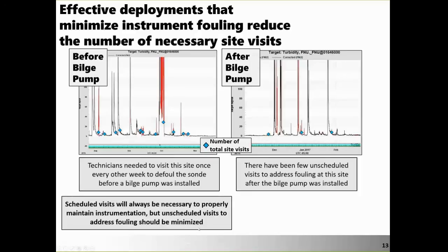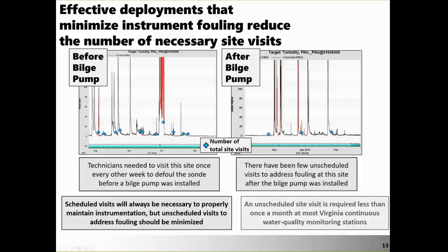There will always be scheduled visits necessary to properly maintain instrumentation, but we're trying to minimize unscheduled visits — those times we come in and see the records don't look accurate and someone has to drive out to clean the instrument. Our deployments that are running really well have unscheduled site visits less than once a month. If someone is going out every week or few days to clean the instruments, there's something that can be improved.